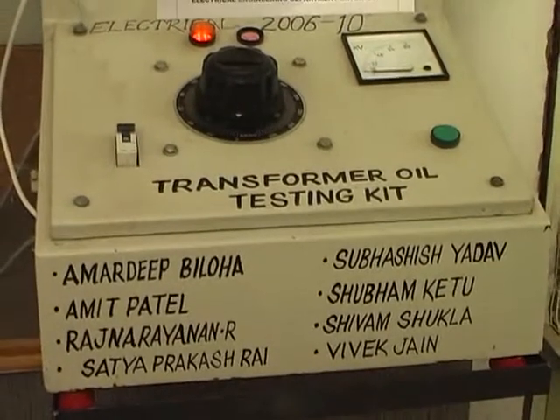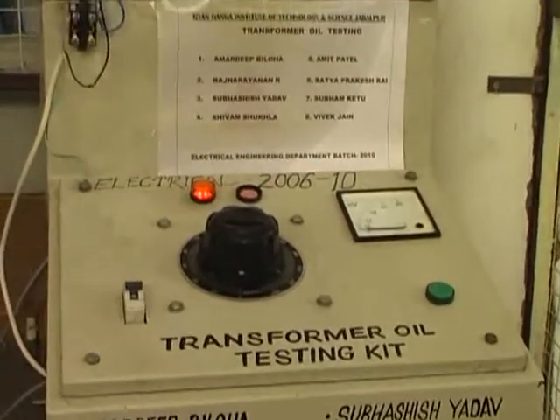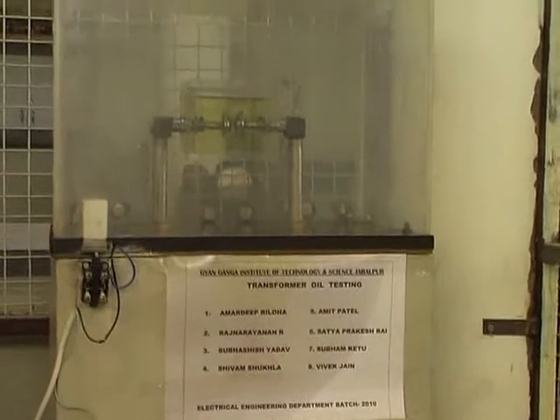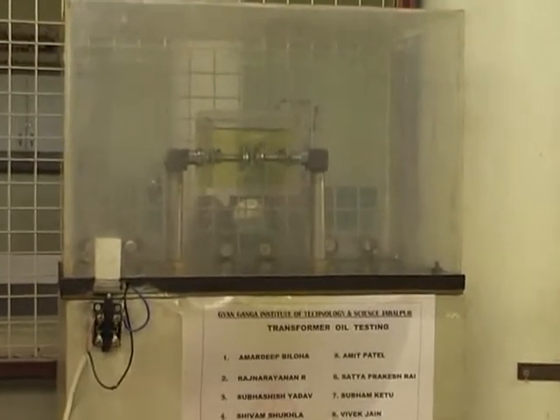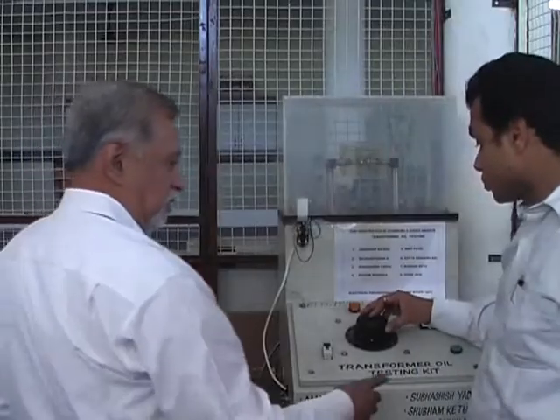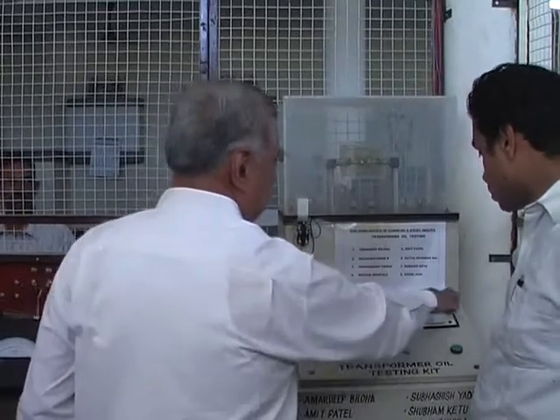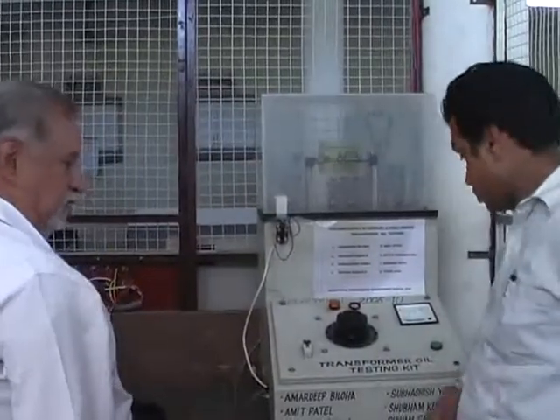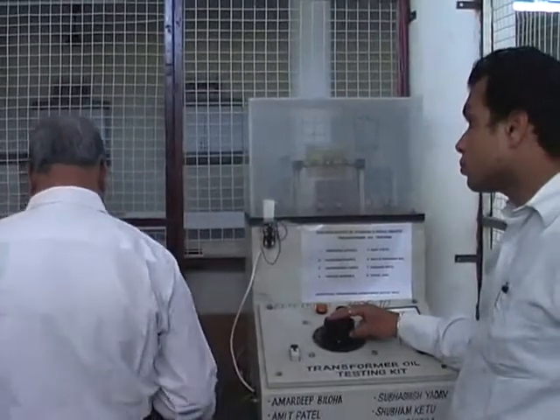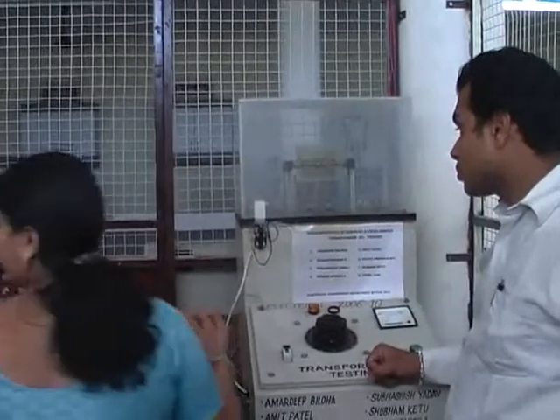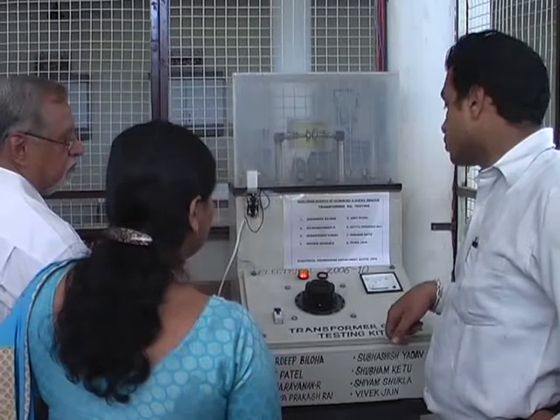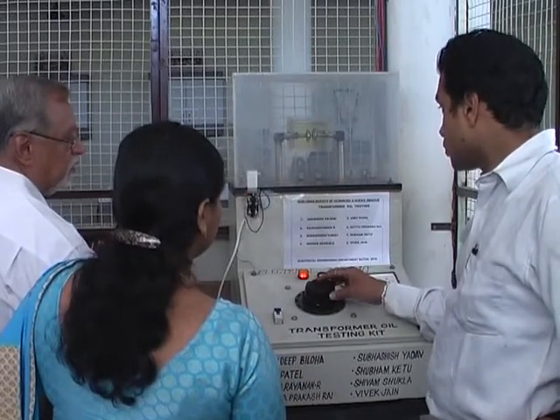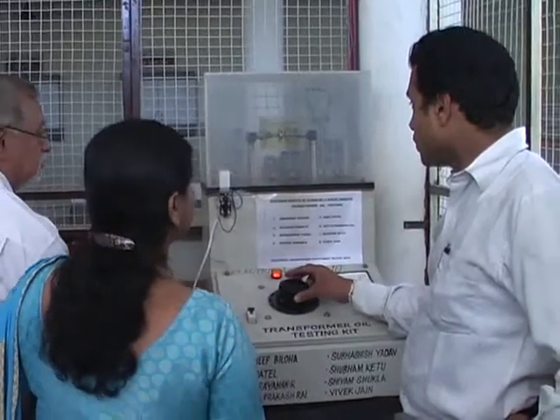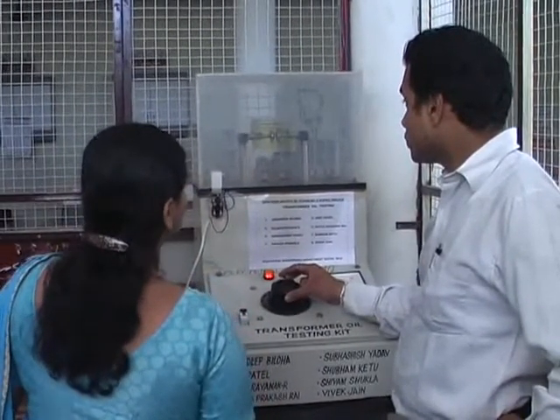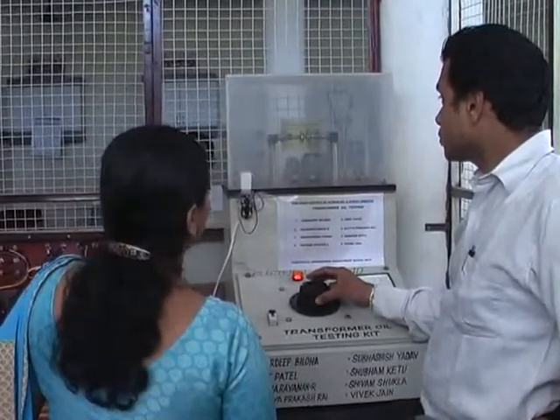This is transformer oil testing kit, which is used for measurement of breakdown voltage of transformer oil. On the top of the unit, there is an oil test cell, which is filled with the oil which is under test. The sphere gaps have been designed as per the requirement of IS applicable for breakdown voltage testing of oil, and this test kit is able to develop up to 90 kilovolts, that is 90,000 volts.